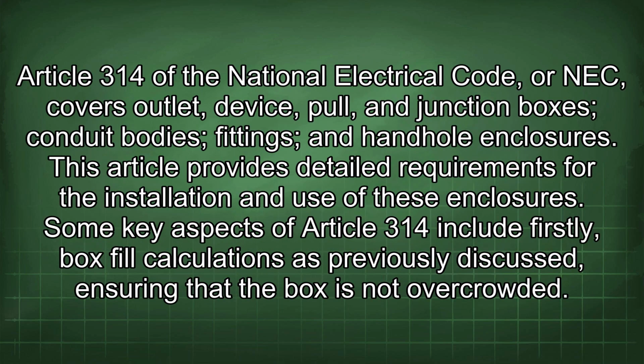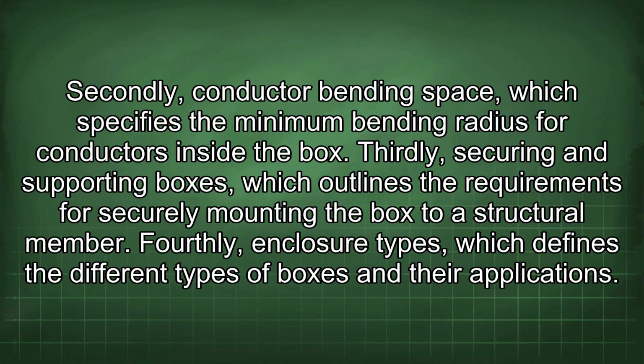Article 314 of the National Electrical Code, or NEC, covers outlet, device, pull, and junction boxes, conduit bodies, fittings, and handhole enclosures. This article provides detailed requirements for the installation and use of these enclosures. Some key aspects of Article 314 include, firstly, box fill calculations as previously discussed, ensuring that the box is not overcrowded. Secondly, conductor bending space, which specifies the minimum bending radius for conductors inside the box. Thirdly, securing and supporting boxes, which outlines the requirements for securely mounting the box to a structural member. Fourthly, enclosure types, which defines the different types of boxes and their applications.